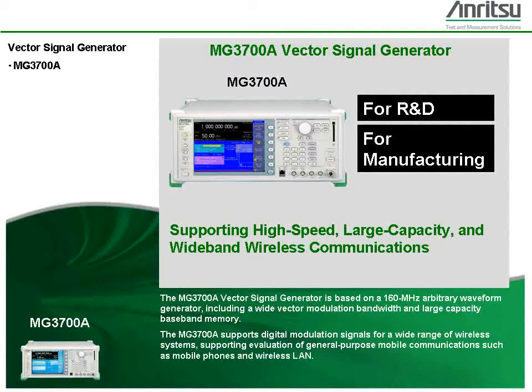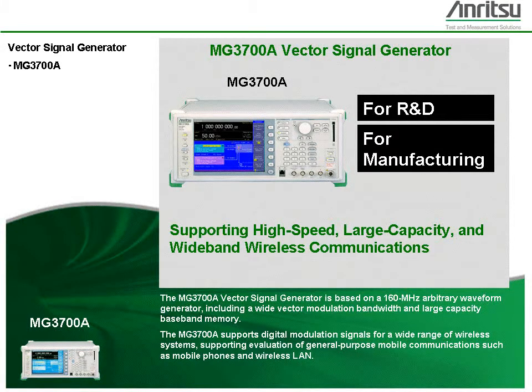The MG3700A vector signal generator is based on a 160 MHz arbitrary waveform generator, including a wide vector modulation bandwidth and large capacity baseband memory. The MG3700A supports digital modulation signals for a wide range of wireless systems, supporting evaluation of general-purpose mobile communications such as mobile phones and wireless LAN.